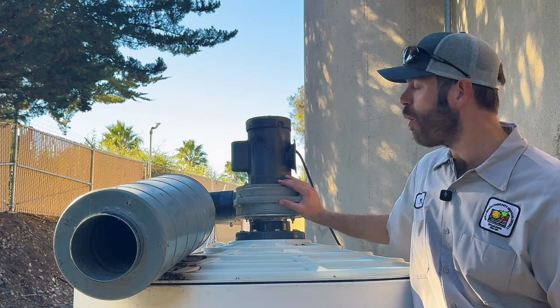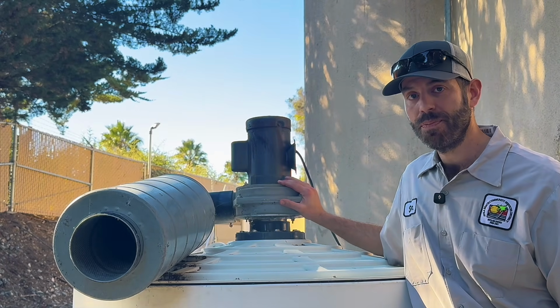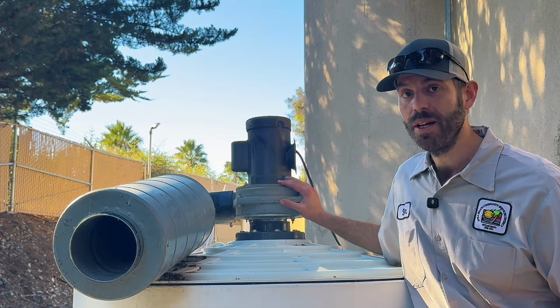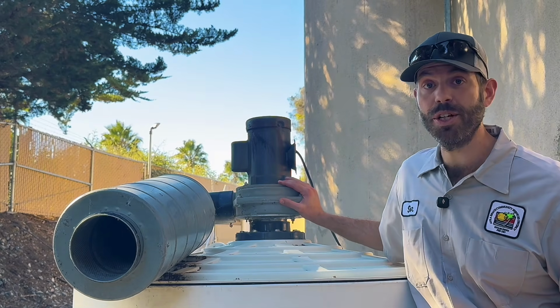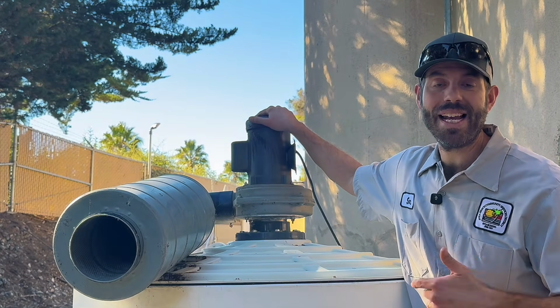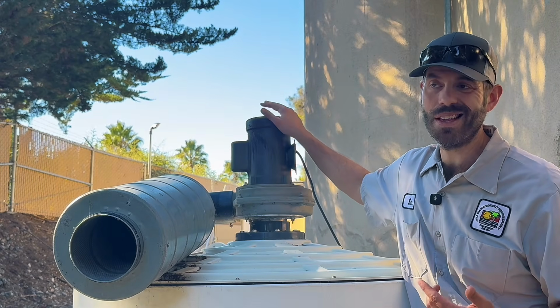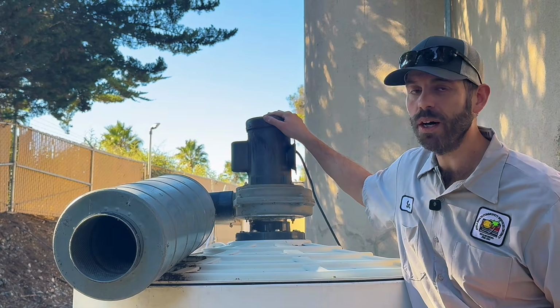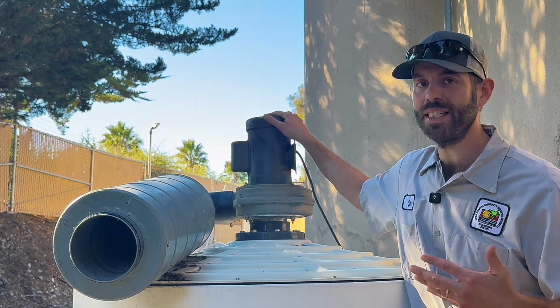So this blower has started to make rattling sounds. It's in continuous operation and it's been running for about 6 years straight, okay? But this is a bearing that cannot be greased on this particular motor. It's not a very big blower, it's not a very big motor. So it's gonna be actually a fairly easy swap.